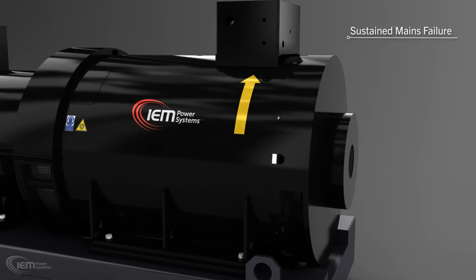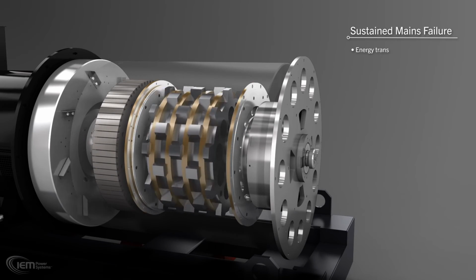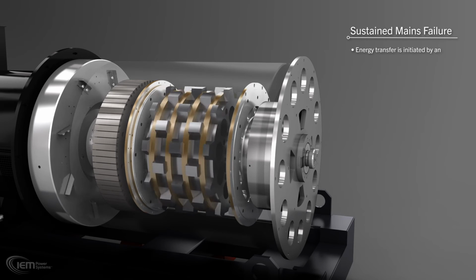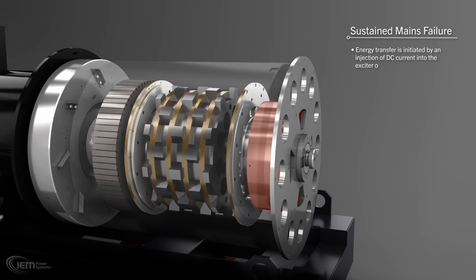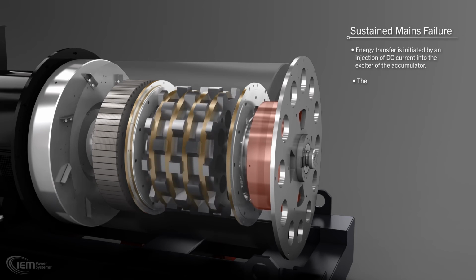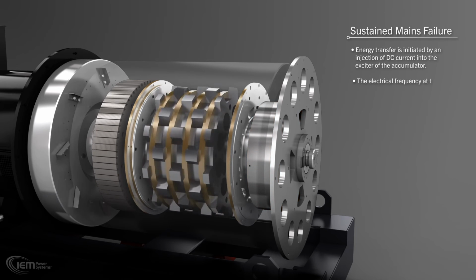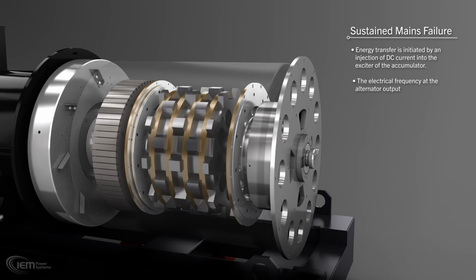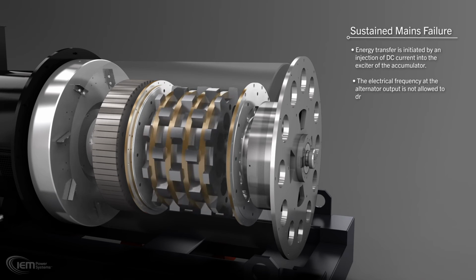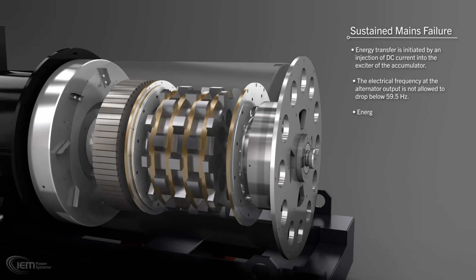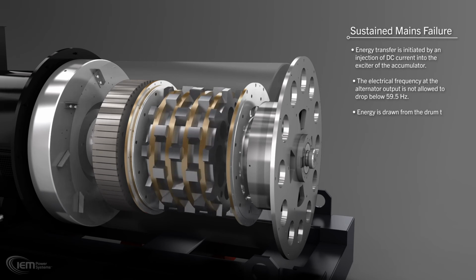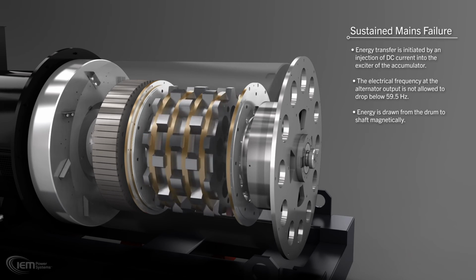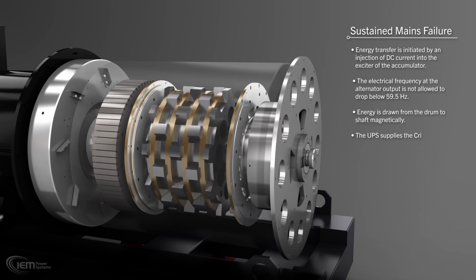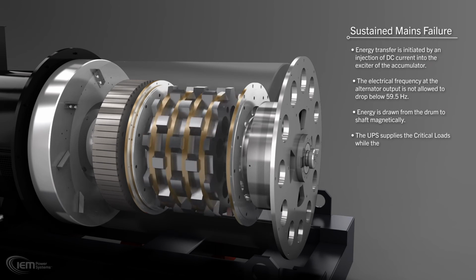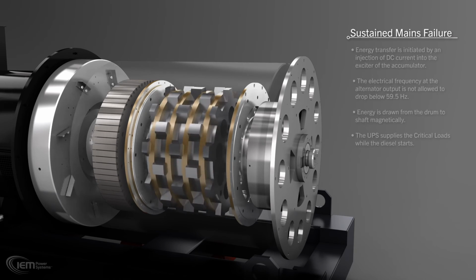Sustained mains failure. During sustained mains failure, the energy transfer is initiated by an injection of DC current into the exciter of the accumulator. The DC current is injected to maintain the shaft speed so that the electrical frequency at the alternator output never falls below 59.5 Hz. The magnetic coupling of drum and rotor transfers the energy from the drum without mechanical engagement. This patented design provides frictionless energy transfer to supply power to the critical loads while the diesel starts.